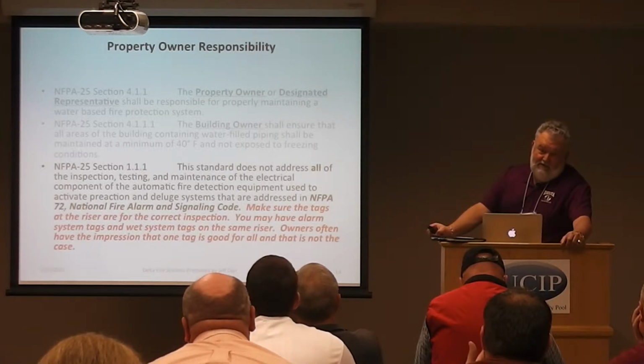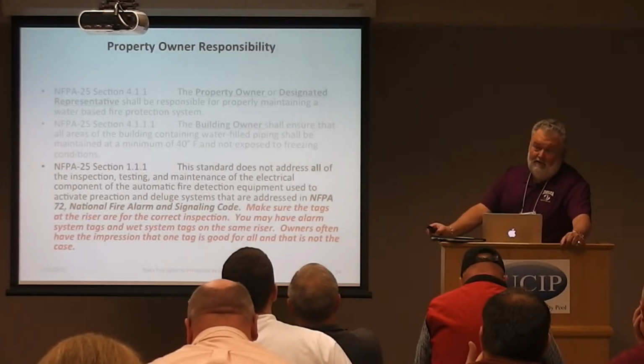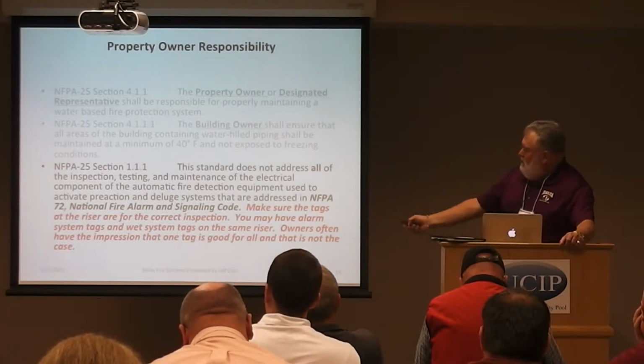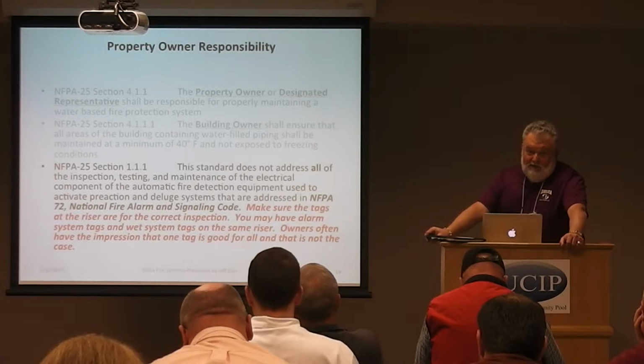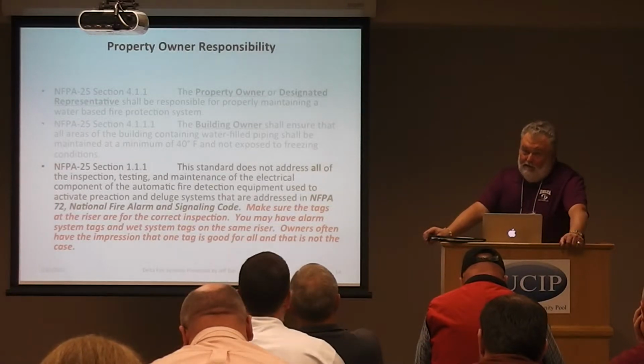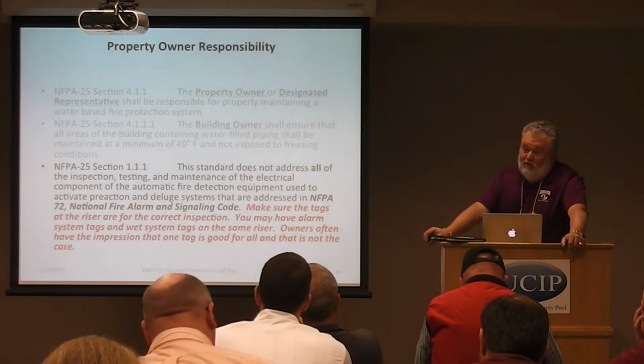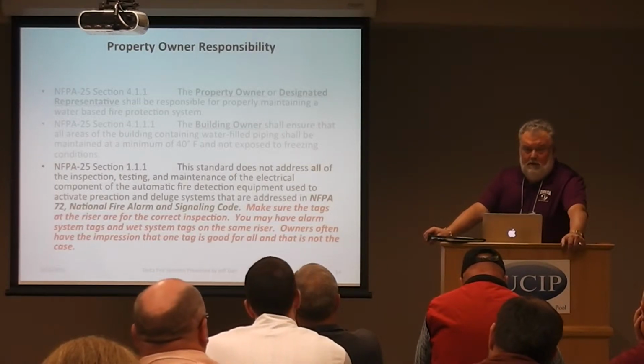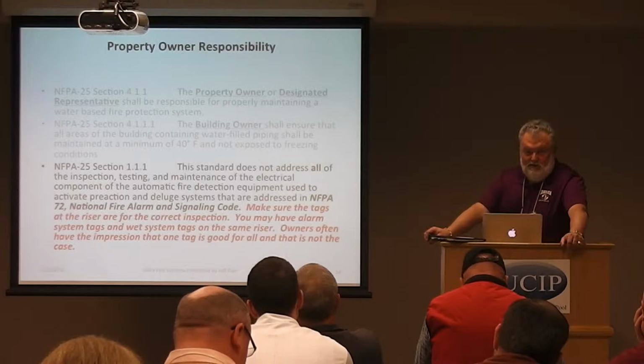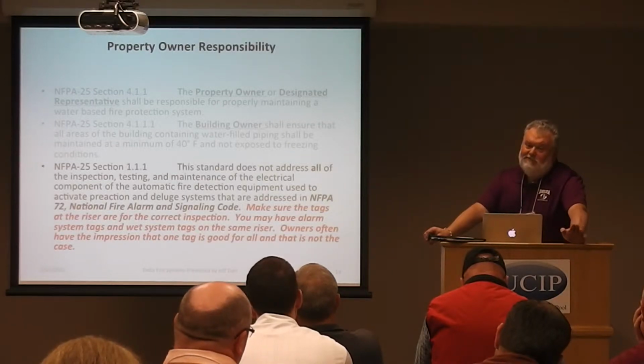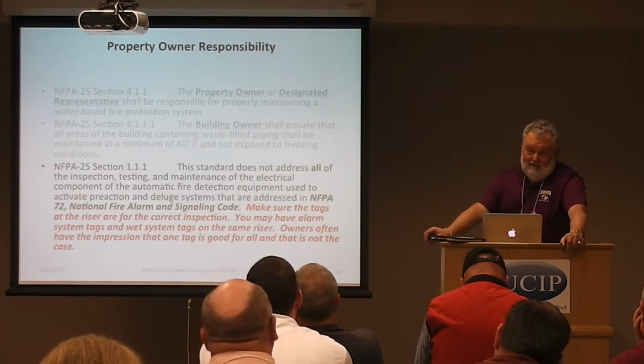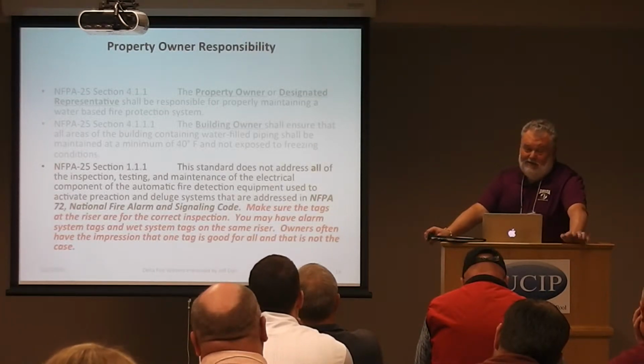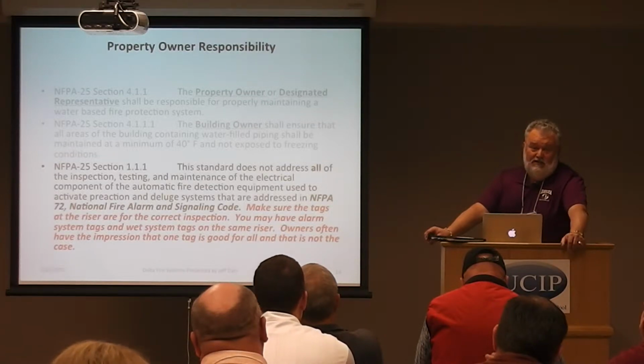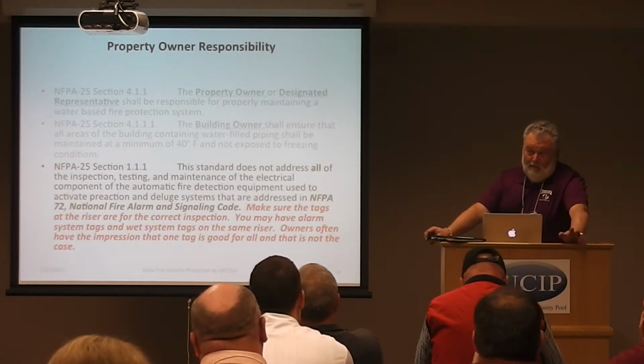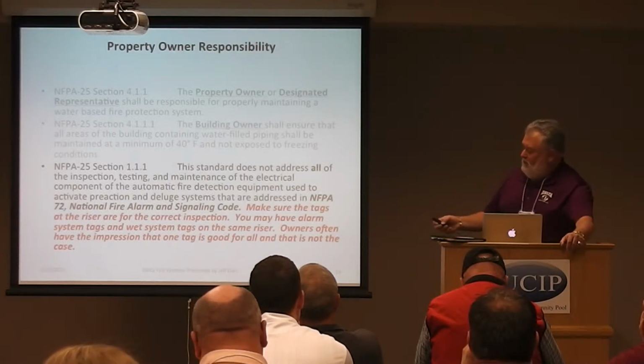Okay, now this section out of NFPA 25, 1.1.1, references us back to the 72 for the detection part of pre-action and deluge systems. One thing you want to make sure of, and there's companies out there, and we run into it all the time, that you go in and do an inspection and they'll say, well, it's already been done. We had an alarm company here last week. That alarm company only did the alarm portion of that possibly. They did not do the entire system. We ran into that numerous times where an owner thinks that he's covered, he's really not. So be aware that there are some companies out there doing that.